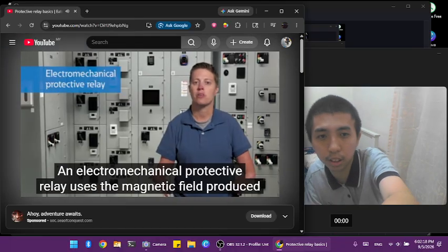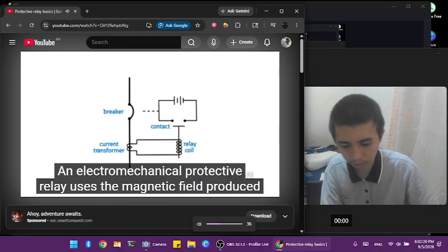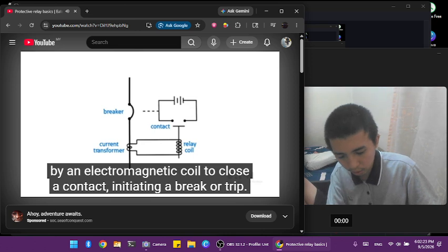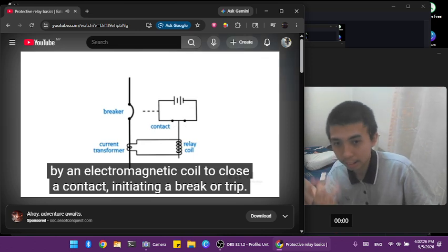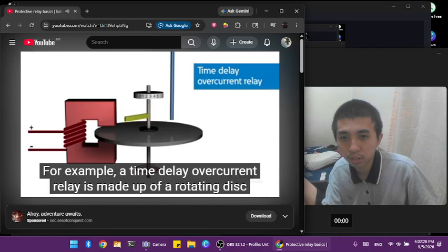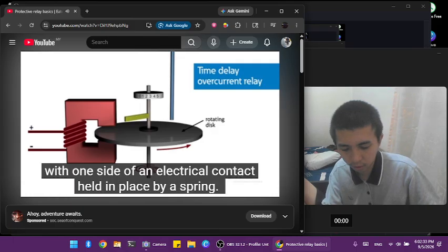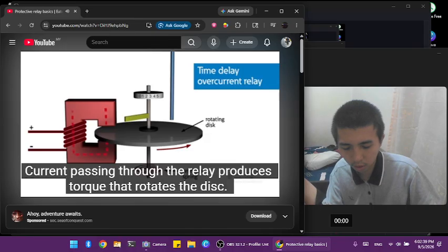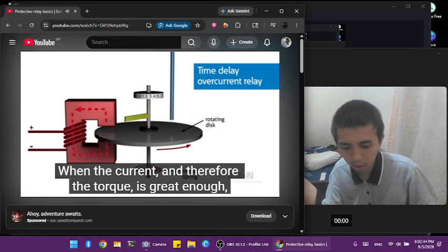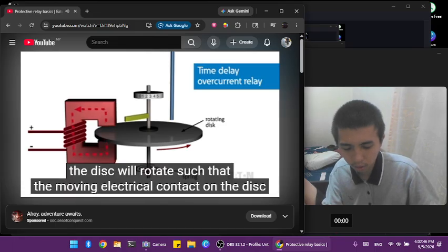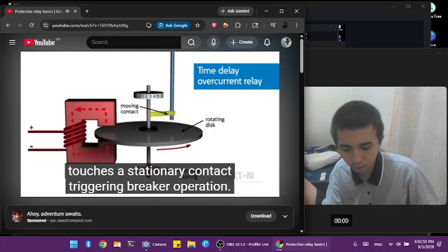An electromechanical protective relay uses the magnetic field produced by an electromagnetic coil to close a contact, initiating a breaker trip. For example, a time delay overcurrent relay is made up of a rotating disc with one side of an electrical contact held in place by a spring. Current passing through the relay produces torque that rotates the disc. When the current, and therefore the torque, is great enough, the disc will rotate such that the moving electrical contact on the disc touches a stationary contact, triggering breaker operation.